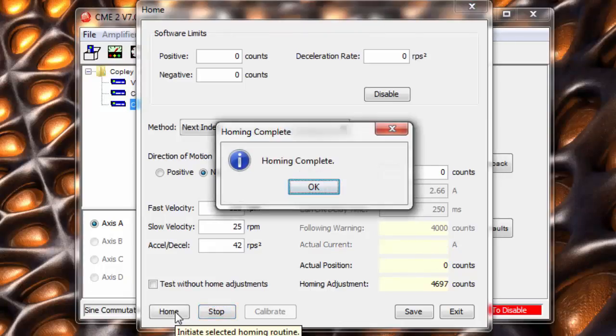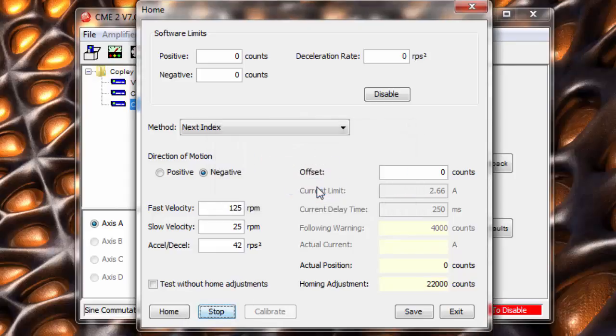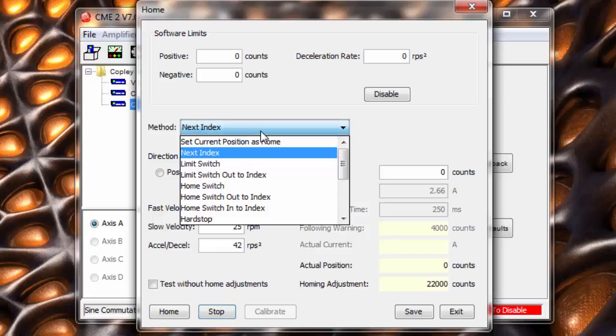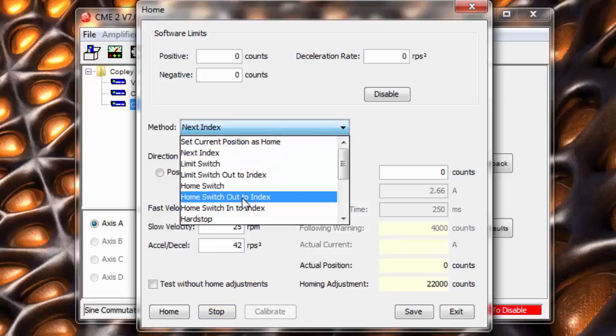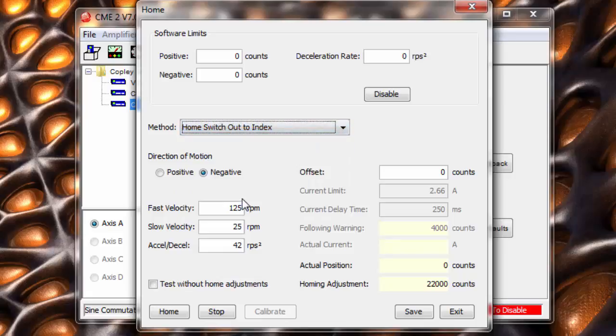For this reason, we now set up the third method of homing, which is a combination of the home switch and the index pulse. This gives us the repeatability of the index pulse, but we only use the index pulse nearest the home switch, so we always home to the same turn of the servo motor.